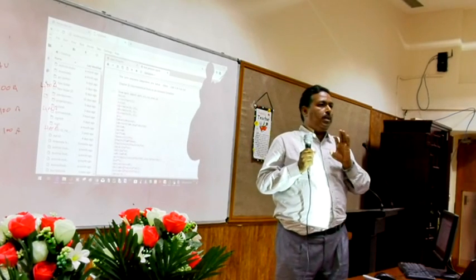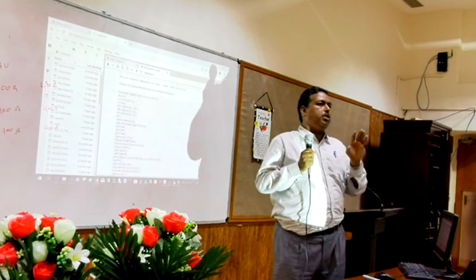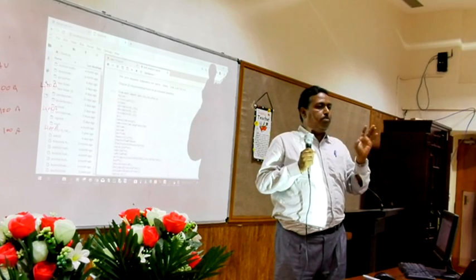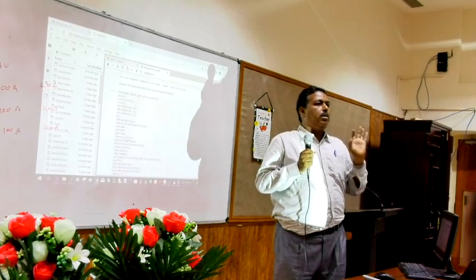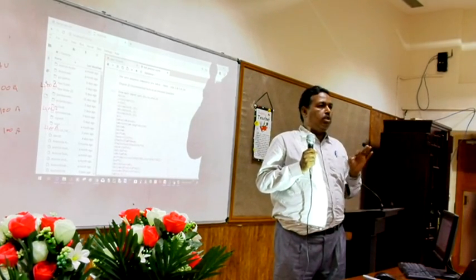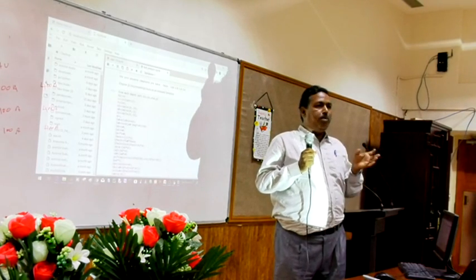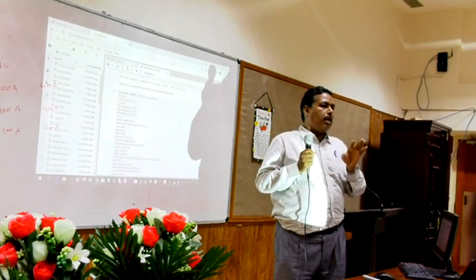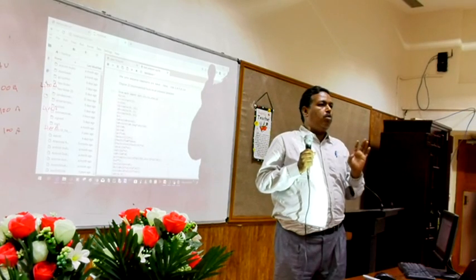Fourth unit, unsymmetrical fault analysis using symmetrical component. Symmetrical component is nothing but positive, negative and zero sequence, and it will be used for finding the fault current for line to line, line to ground, double line to ground, and line to line fault.